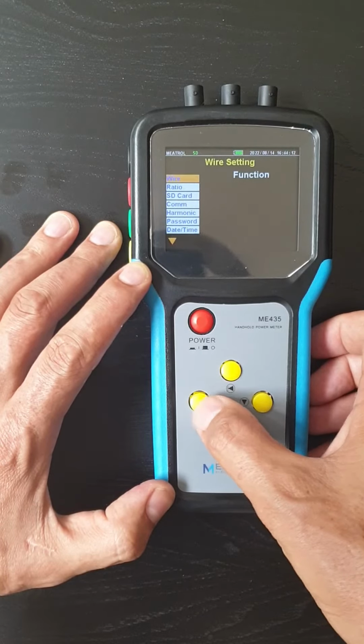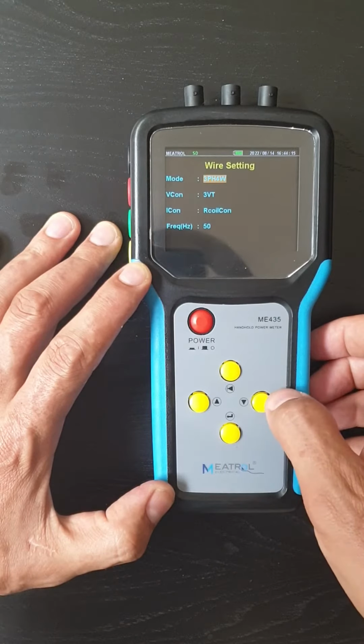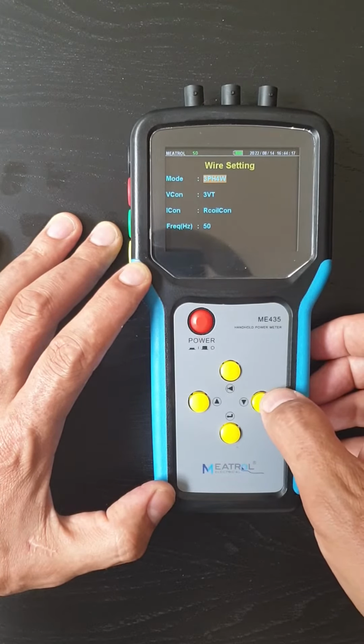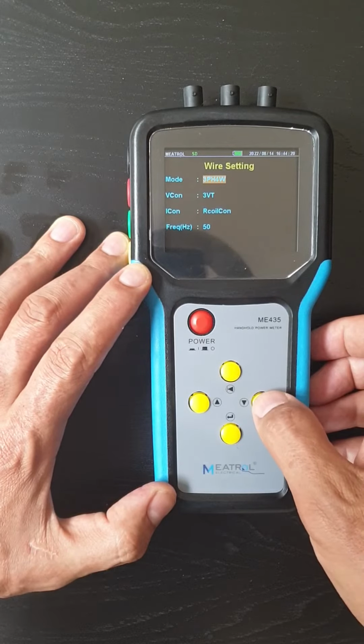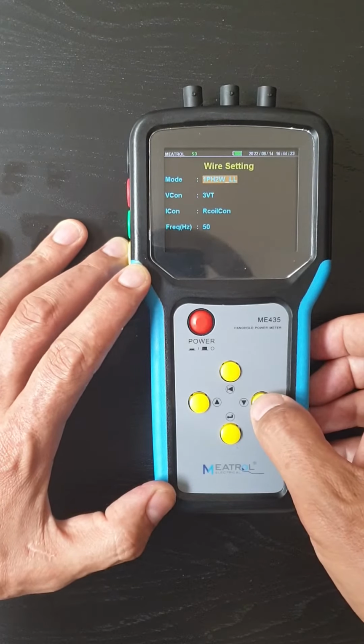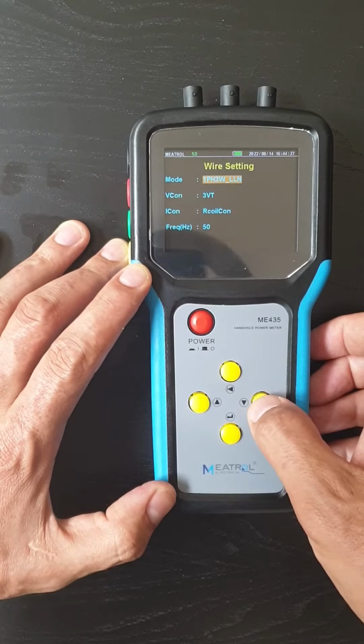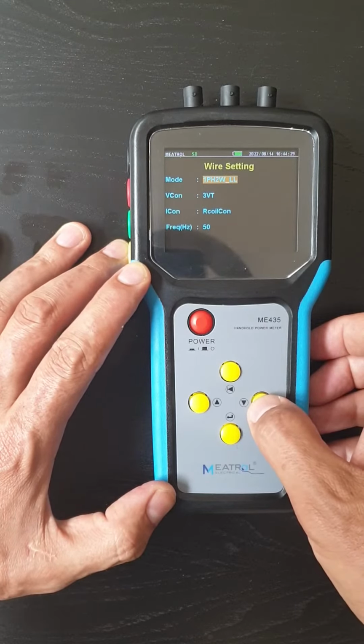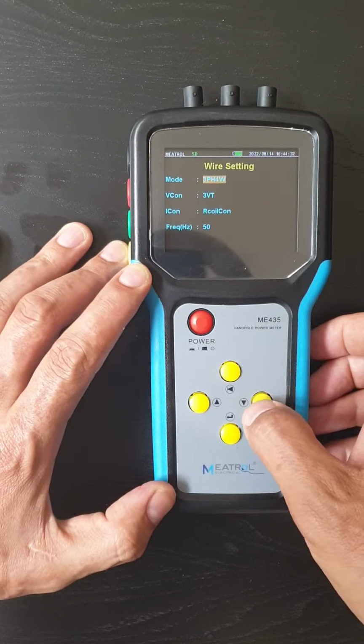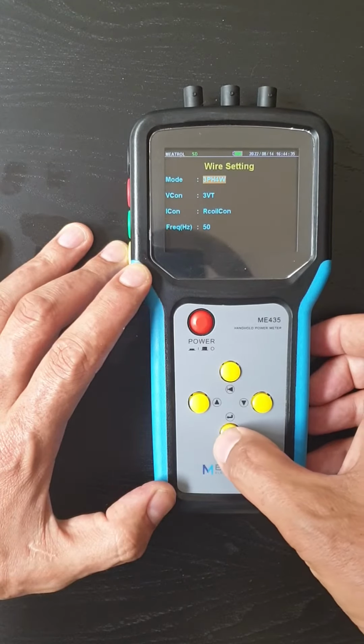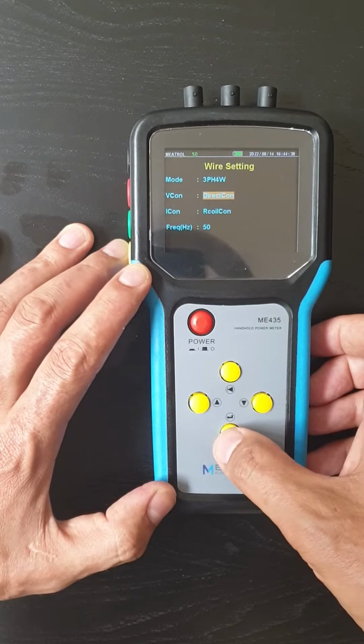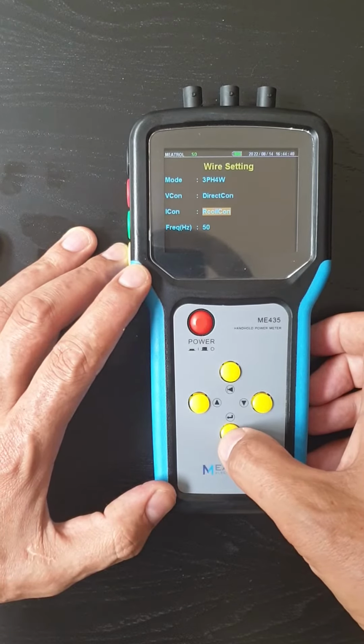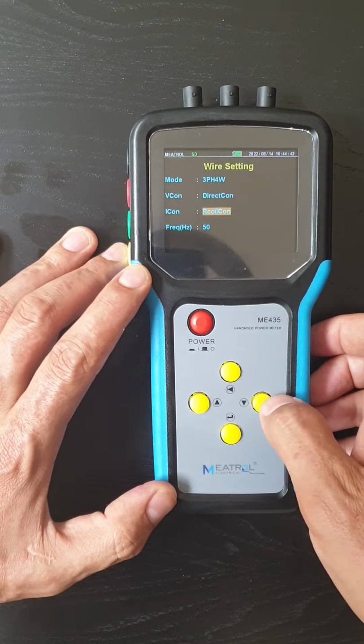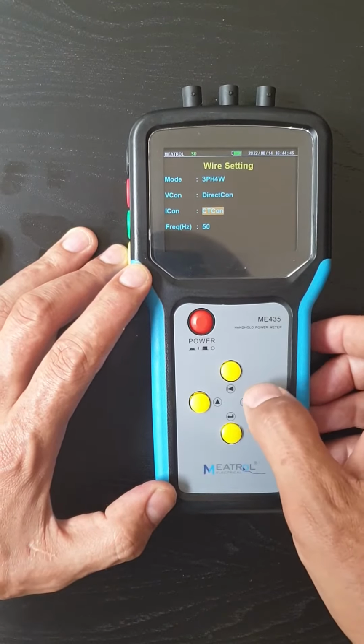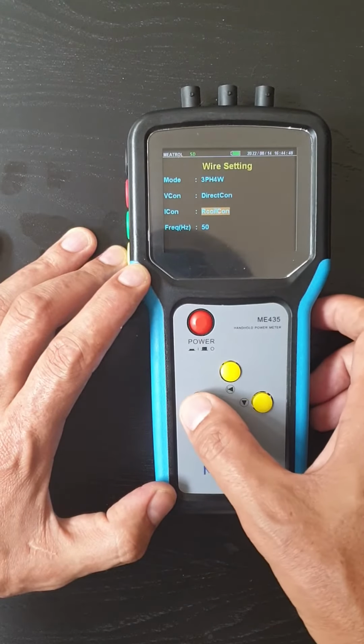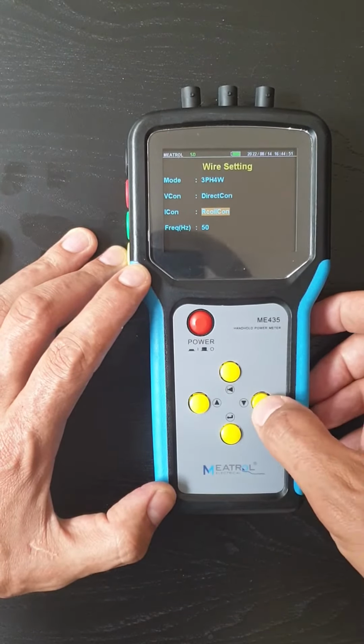Okay, so let's start at the beginning. Wire. So we can select the mode. So 3-phase 4-wire is the most common setting. You can also get 1-phase 2-wire and a few other settings. Okay, so let's leave it on 3-phase 4-wire. So voltage connection, just leave it at direct connection. Then your current connection is either Rogowski coil or current core, solid core CTs. So let's leave it at Rogowski coil.